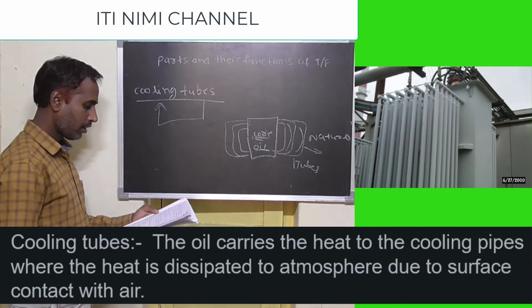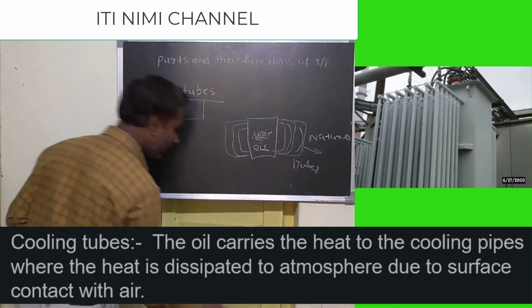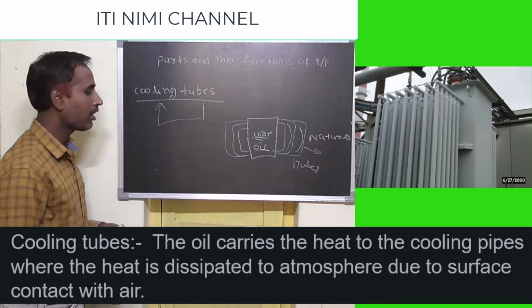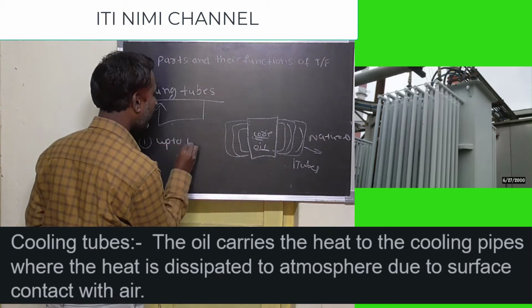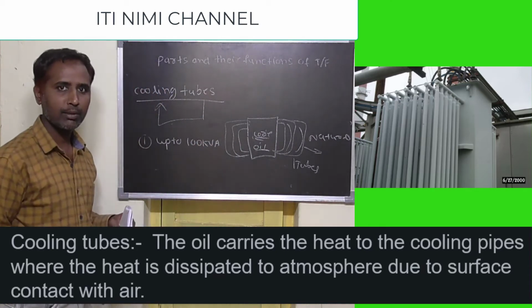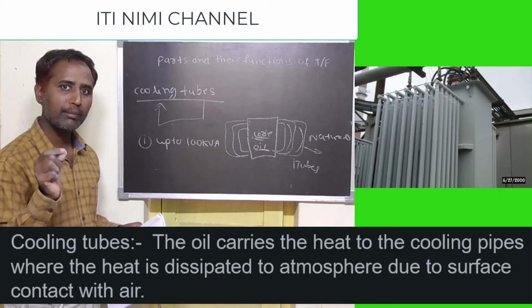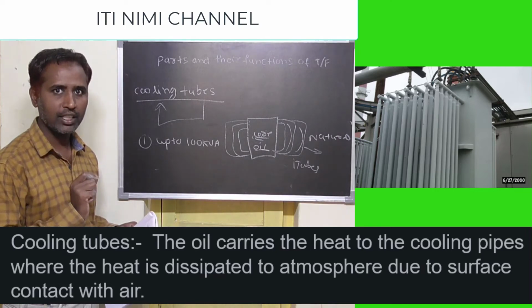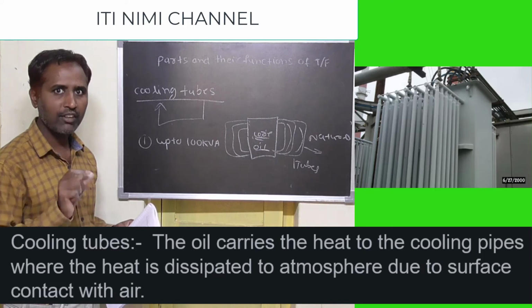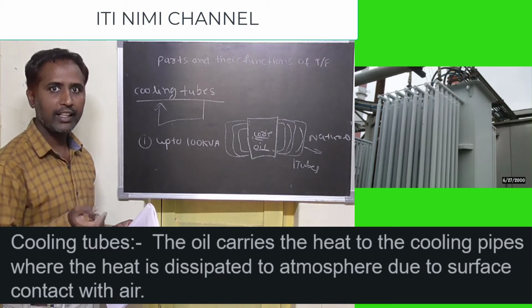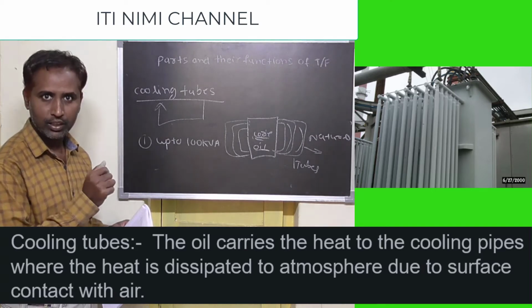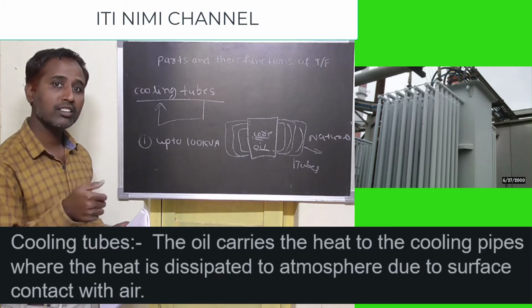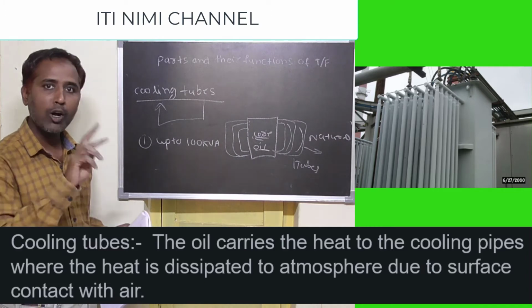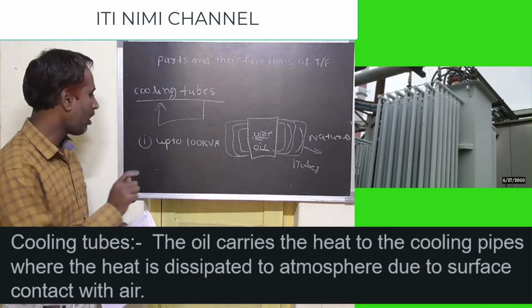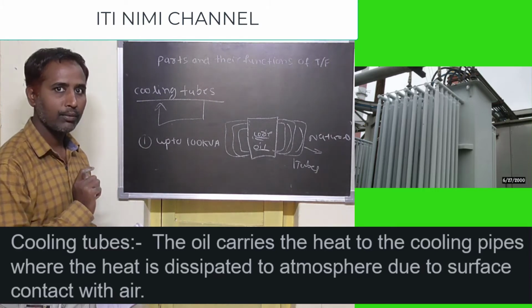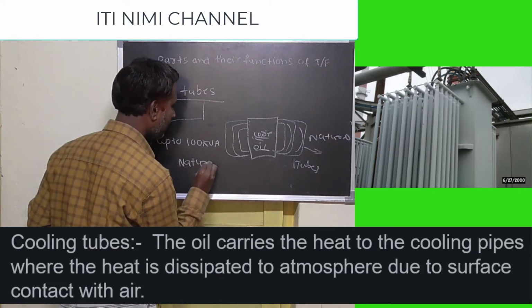In cooling tubes, two questions will come in the examination. First question: up to 100 kVA transformer, which cooling technique or method is used? This question comes because various cooling processes exist, like oil cooling, fresh air natural air cooling, water plus oil cooling, and pressurized water plus oil cooling. Among them, which method is used to cool a transformer up to 100 kVA? The answer is natural cooling.